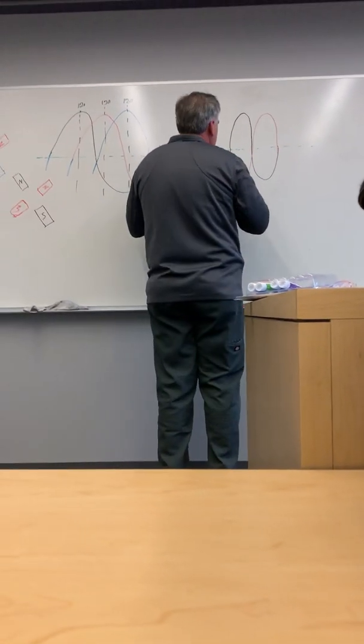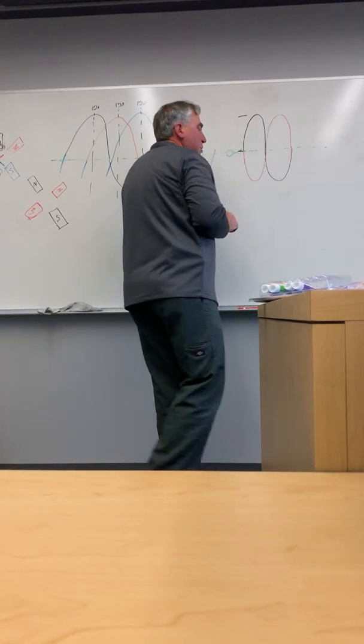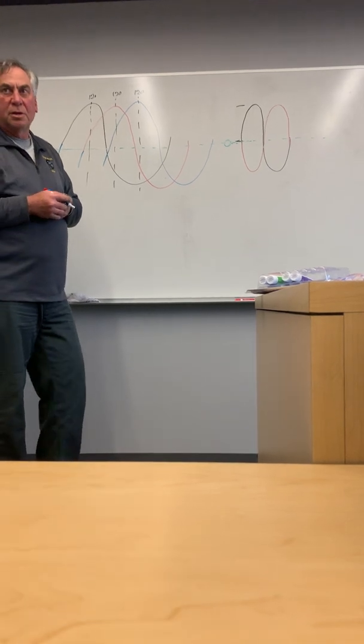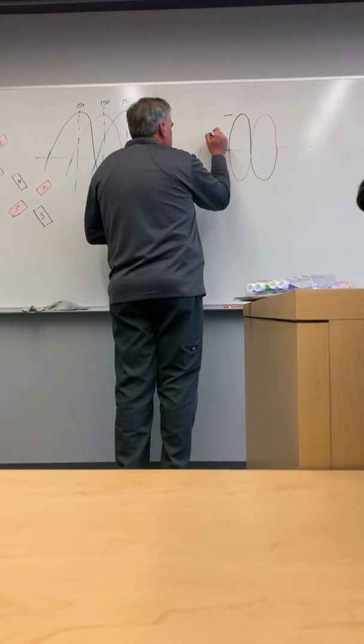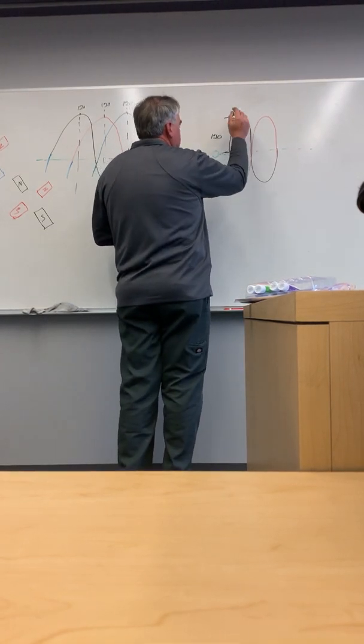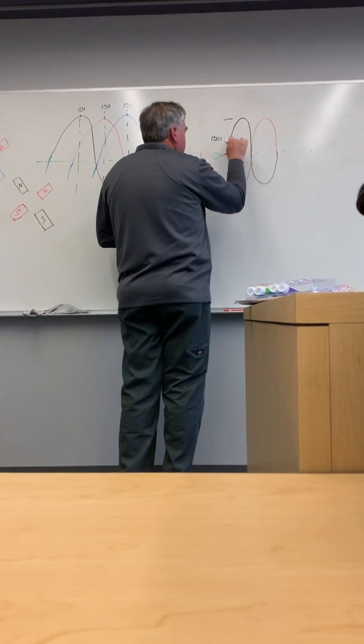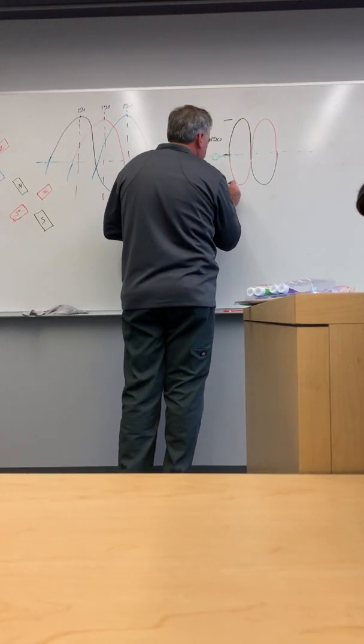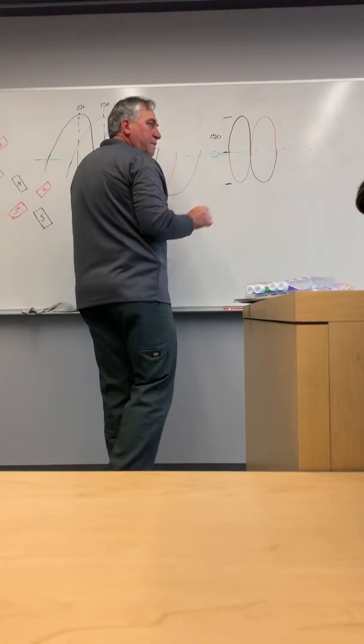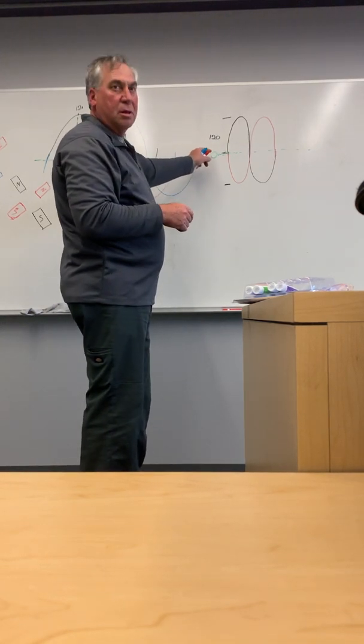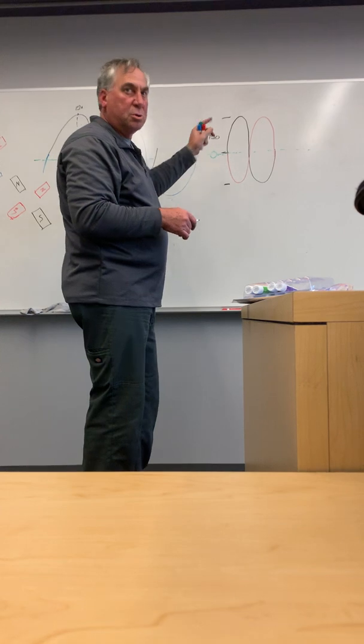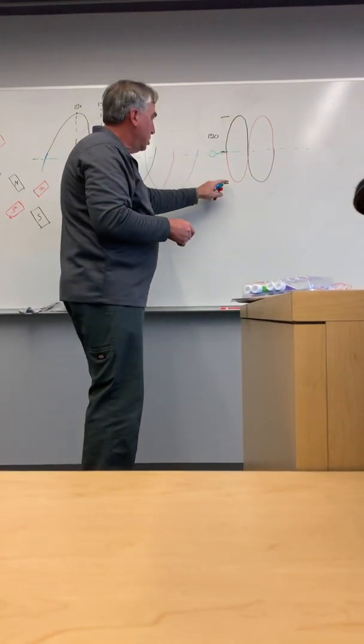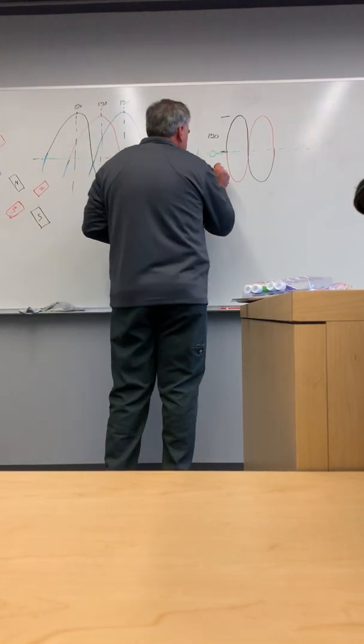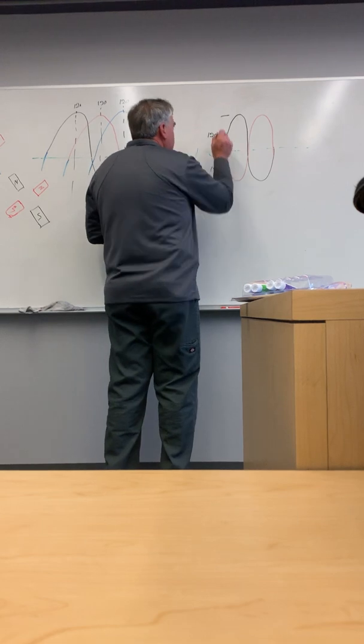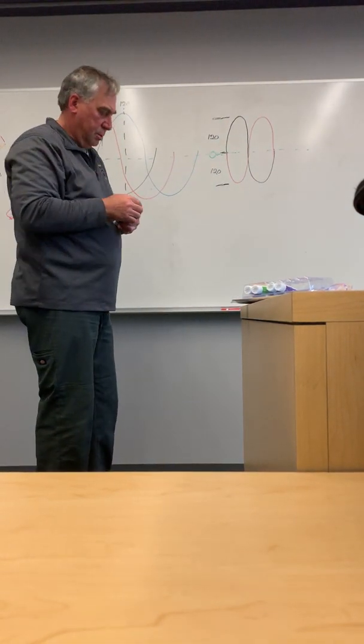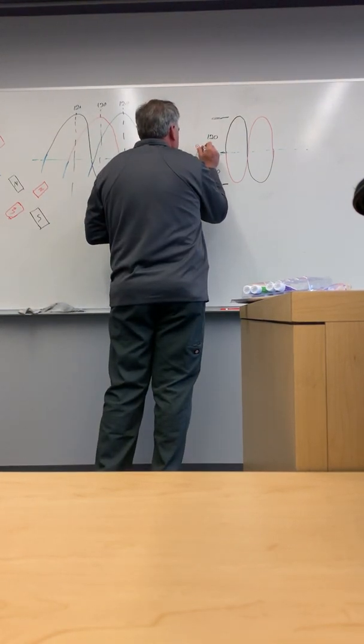Here, you could say from here to here, what is your voltage if we're doing a 120, 240 single phase? This is 120, right? If you're measuring any moment in time from here to here, it's 120. But if we want to measure from here to here, let's say we're checking A phase on a panel to ground or to neutral - one hot to the neutral is going to be 120. Same thing if you go to B phase and check from here to neutral, it's 120. But if you go from here to here and you're hooking up your dryer or your oven, that's 240.